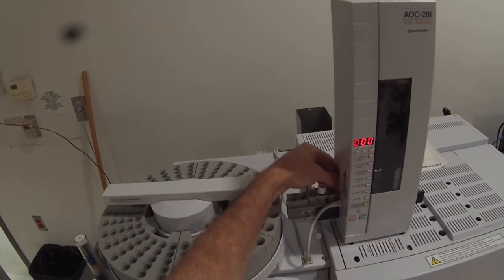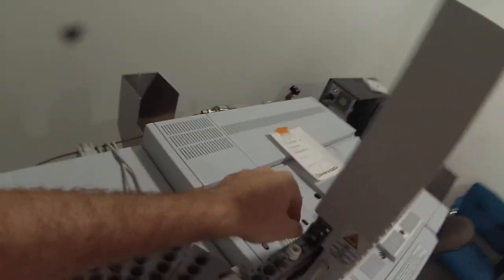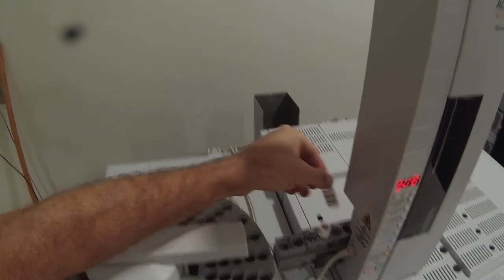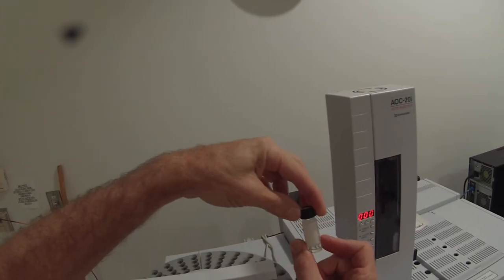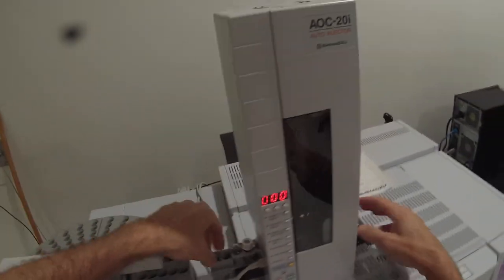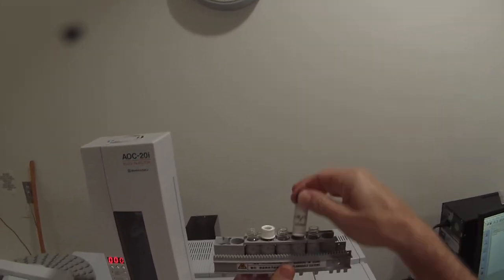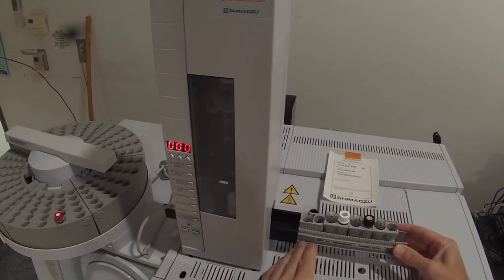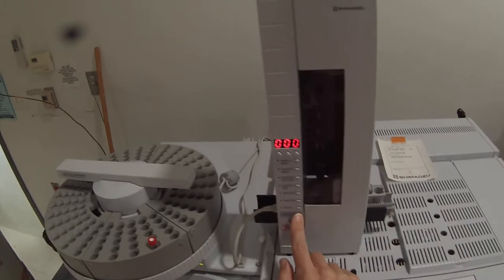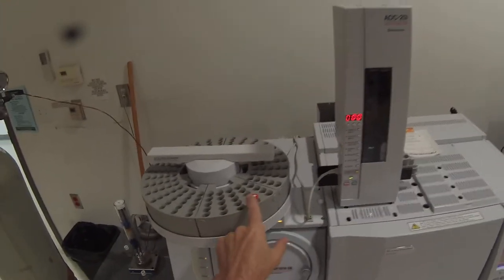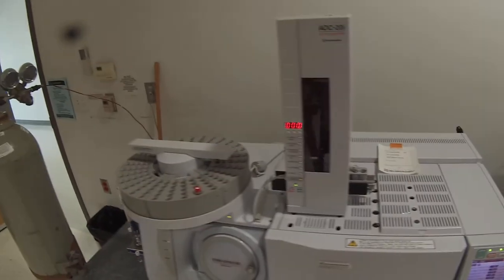I also want to make sure that my second vial here, there's three different vials, 1, 2, and 3 different slots there, I want to make sure that number 2 actually has dichloromethane in it. I refilled this earlier this morning. Pull that rack out so you can see it. So we've got a solvent and a waste, a solvent and a waste. So this is A, this is B, and this is C. I'm going to be rinsing with just B, which is dichloromethane. C is hexane, and I think A was methanol, but obviously you can see that's not in there right now. So I'm going to reset that so that it'll put that back where it belongs. So we know we're in spot 10. That's important.